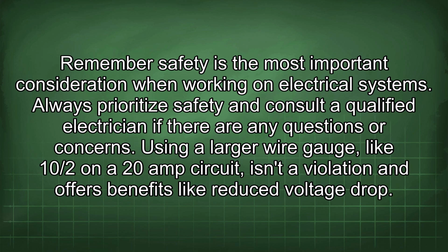Using a large wire gauge, like 10/2 on a 20 amp circuit, isn't a violation and offers benefits like reduced voltage drop.